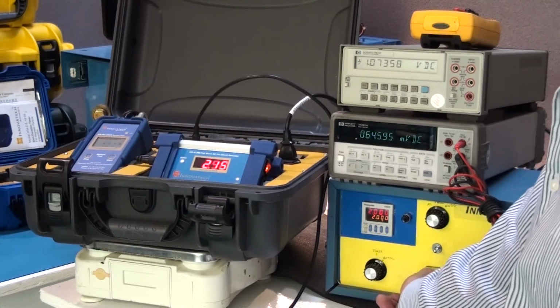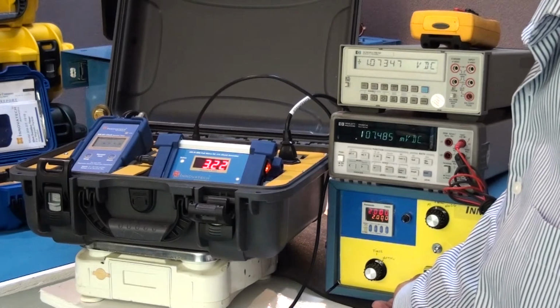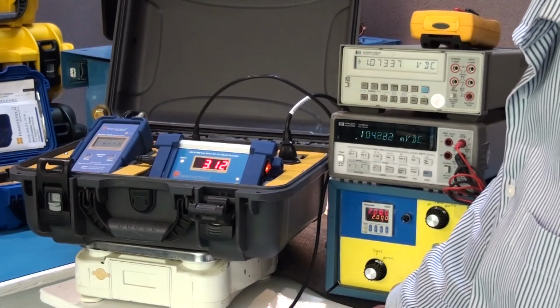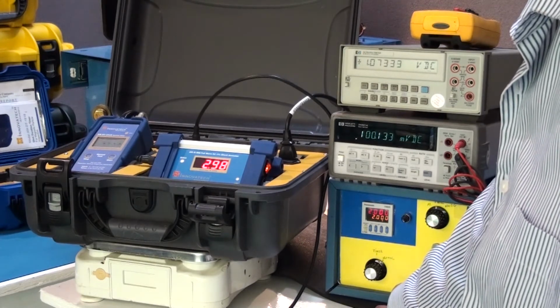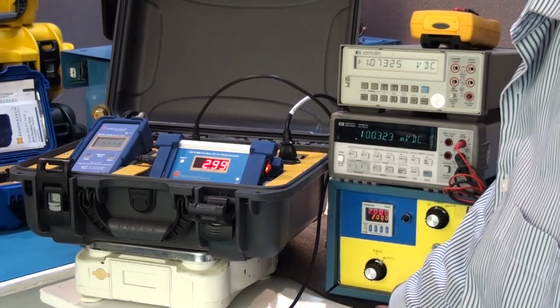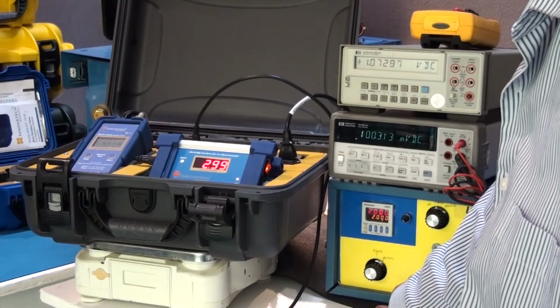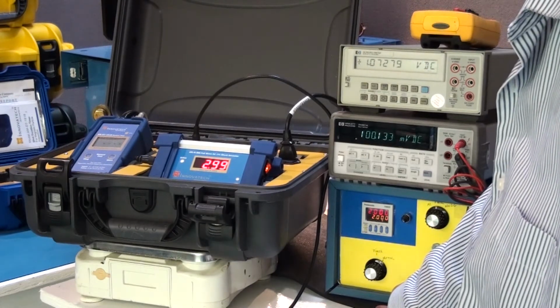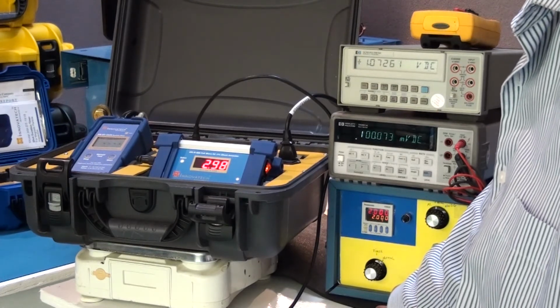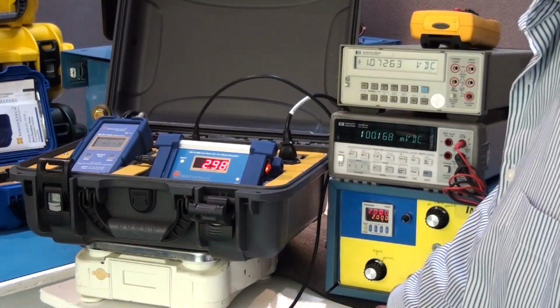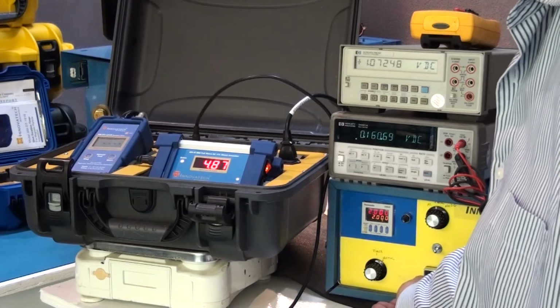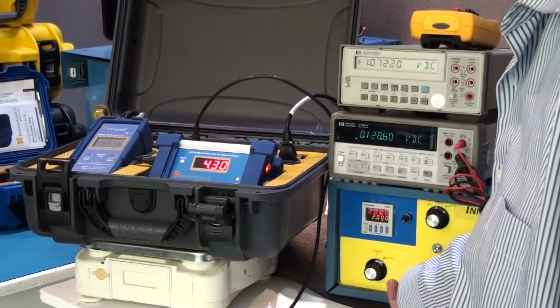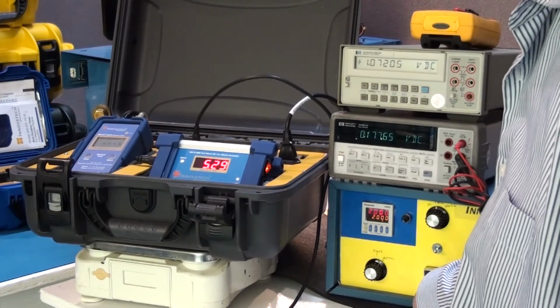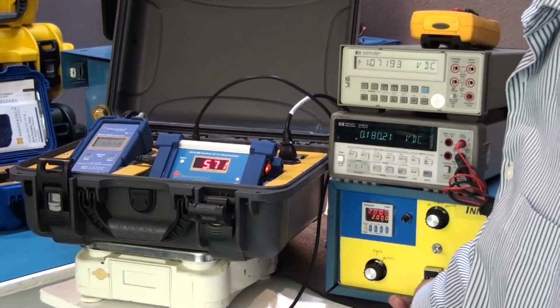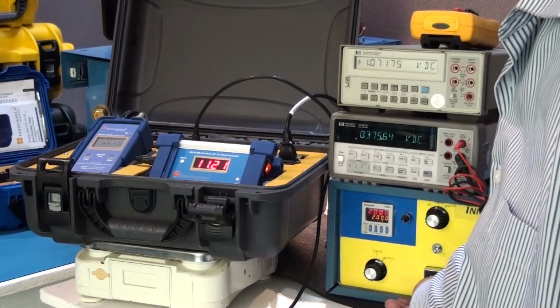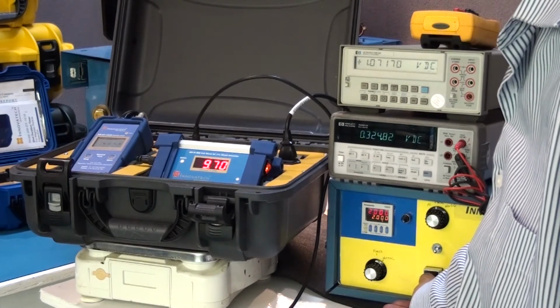Okay, now we'll run this up to 100 millivolt, which should be 3K, or 3,000 amperes on the meter. So we're at about 2.99, which is well within spec, well within a 1% accuracy. 2.98, well within the 1% accuracy. Let's run it up to 10K. That'll be 0.33 volts input. And this is calibrated as a means average meter, averaging meter.